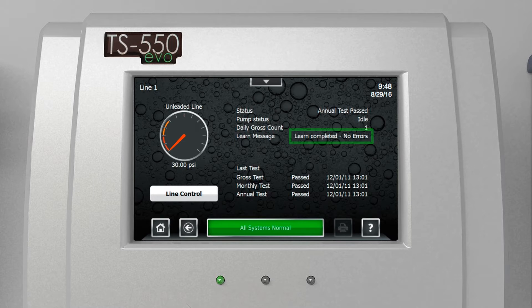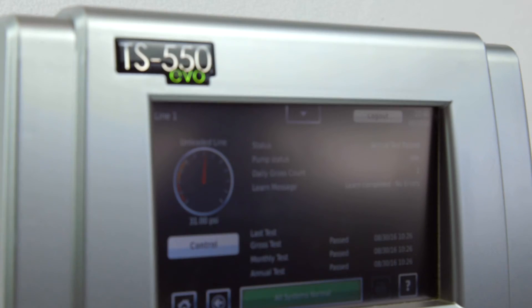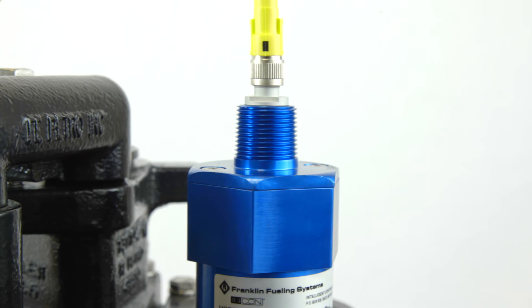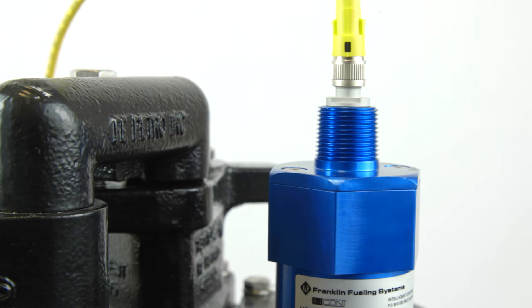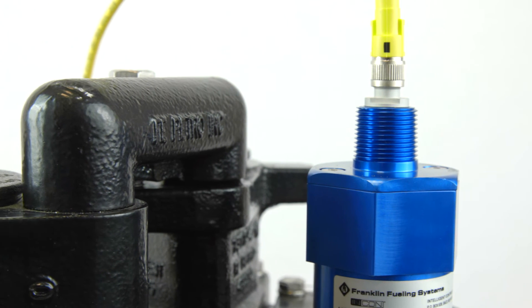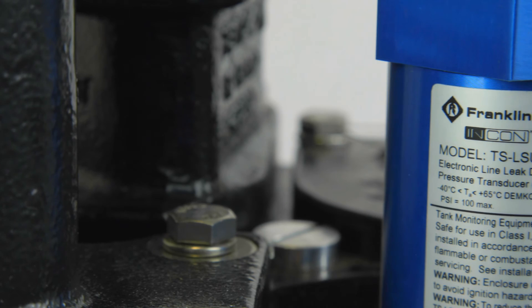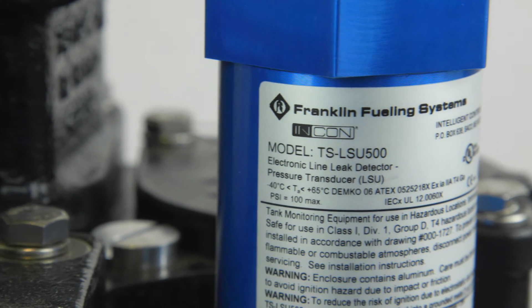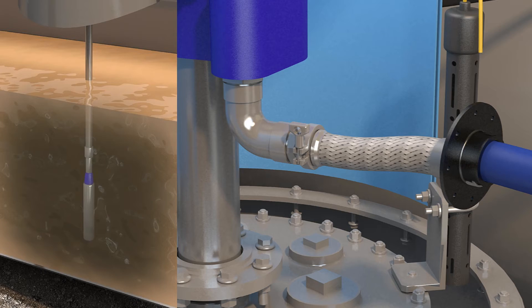The combination of our electronic line leak with auto-learn technology allows us to support higher piping capacities than most. We can handle 312 gallons of rigid piping and up to 95 gallons of flexible piping, and those values can be combined if you have a circumstance where you need longer distances.